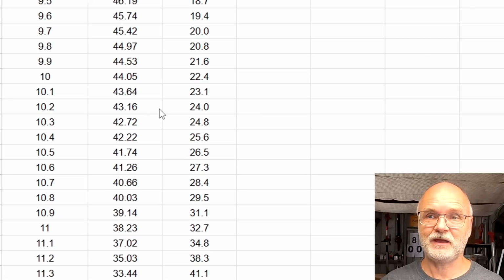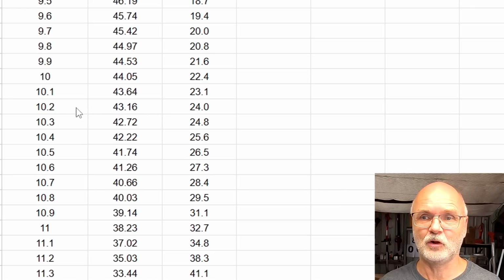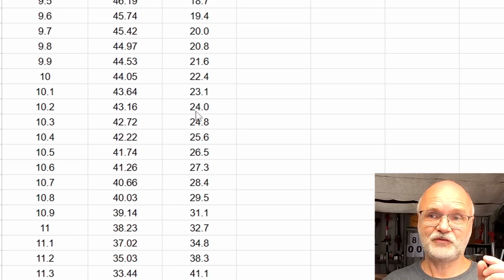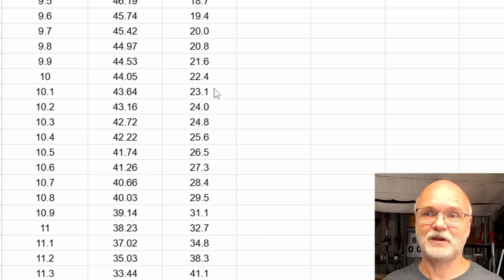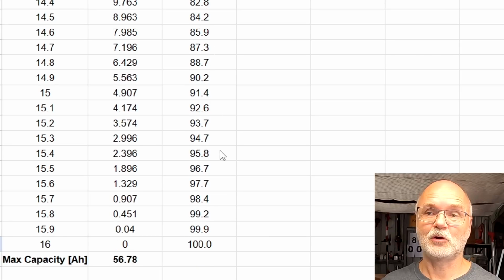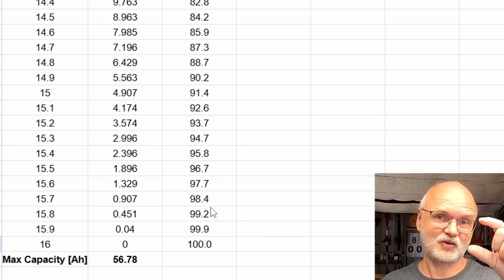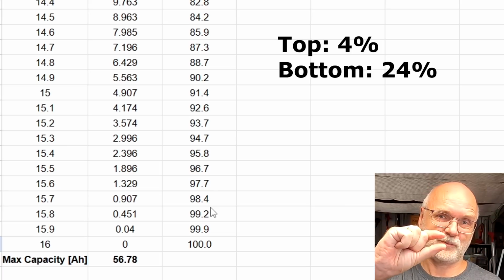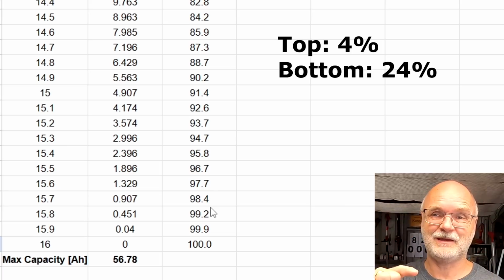And then we discharged the battery all the way down to 10.2 volts. This is what the smart shunt measured directly at the battery, and this is a capacity of around 24%. So we cannot use any of this remaining 24% in the battery, and we can also not use any of this remaining 4% at the top. So 24% at the bottom and 4% at the top makes 28%.